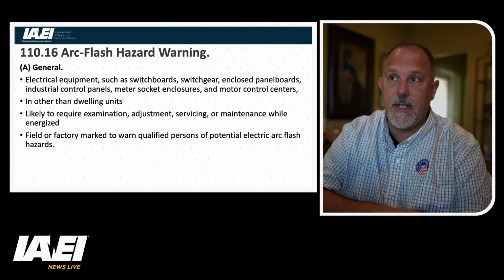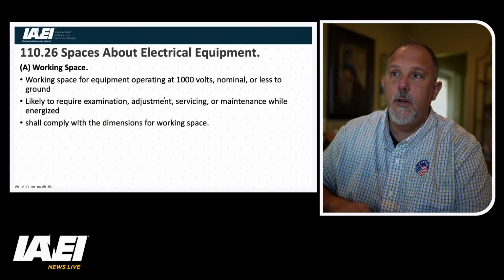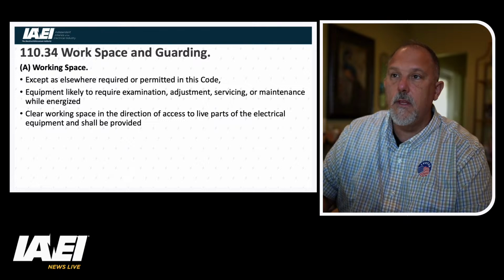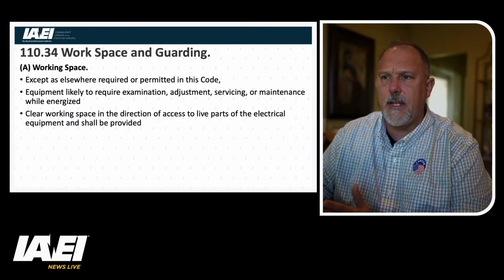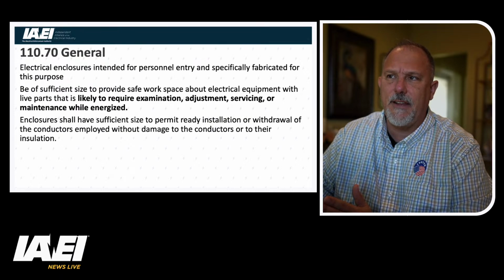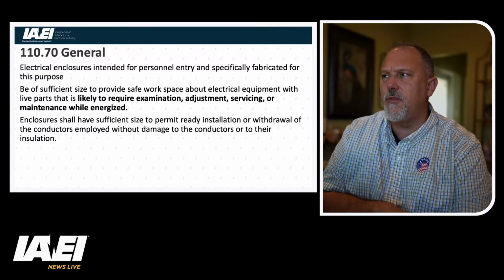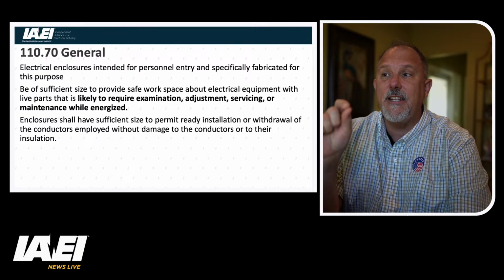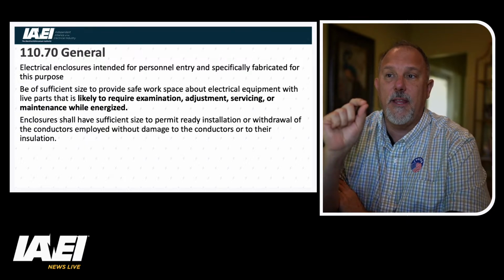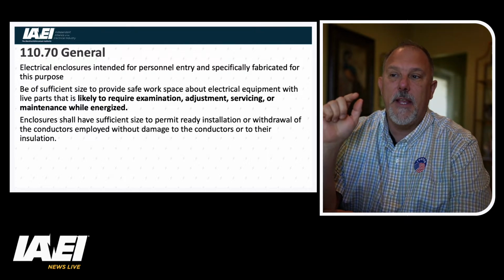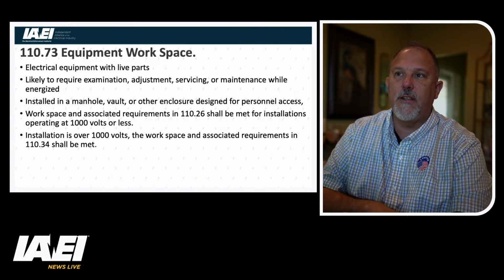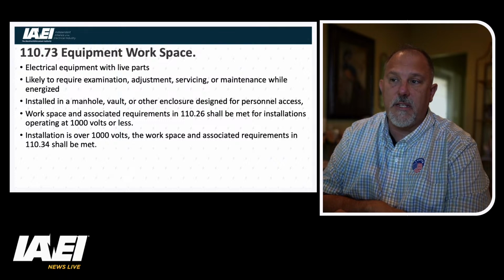But 110.16 is another place where it is used. 110.26 we already talked about. 110.34, I think now you're getting into the medium voltage stuff. 110.70, electrical enclosures intended for personnel entry and specifically fabricated for the purpose be of sufficient size to provide safe work space about electrical equipment with live parts that is likely to require examination, and then the enclosures have to have sufficient size. And then 110.73, that's your medium voltage working space. It has the same language in there. So we've got to think about all of those areas in the code where that phrase is used, and then look at the equipment.